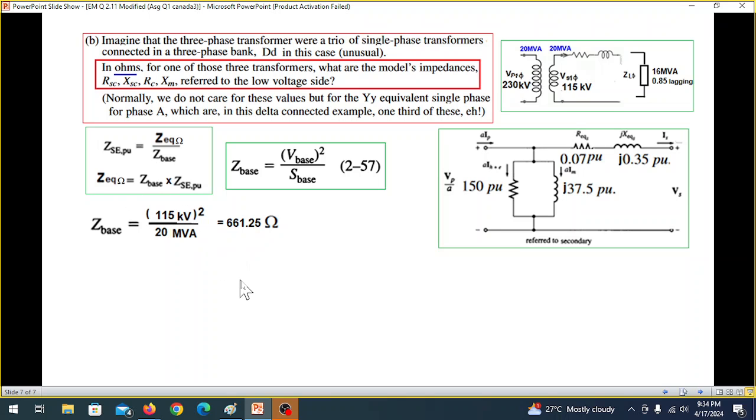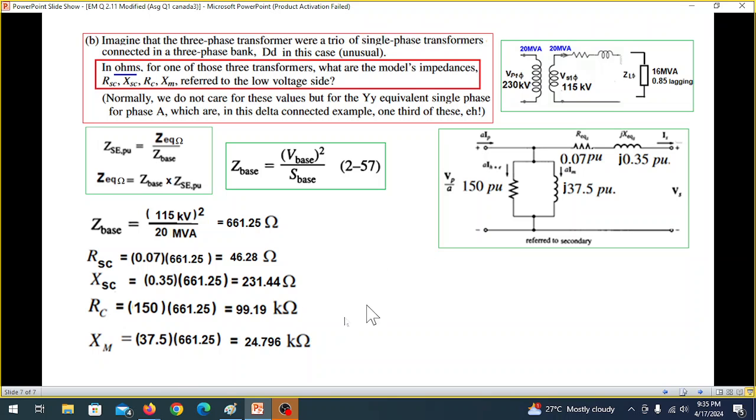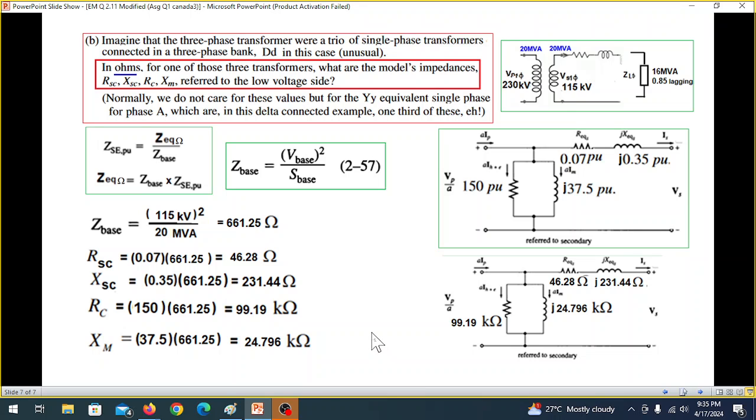Using that, we get this answer that Z-base is 661.25 ohms. And now we can use here to find all the values in ohms. So first of all, R-SC, 0.07 multiplied by Z-base, gives 46.28 ohm. Similarly, X-SC or X-E, 0.35 multiplied by the Z-base gives 231.44 ohms. And similarly, R-C, 150 multiplied by Z-base gives 99.19 kilohms. And X-M is 37.5 multiplied by Z-base gives 24.796 kilohms. So these are the values in ohms. And if you want to write them in the circuit that we have, this becomes in ohms R and X and R and X-M. I hope you have been able to follow this. Please let me know through your comments. Thank you.